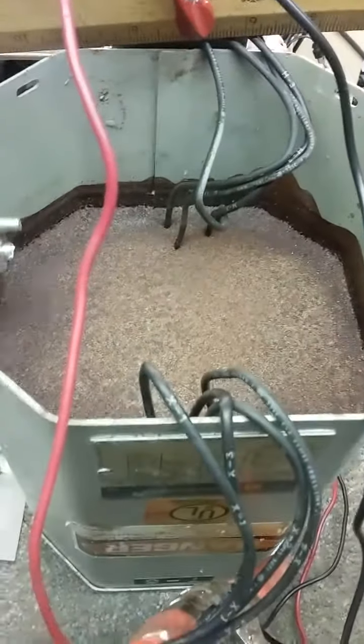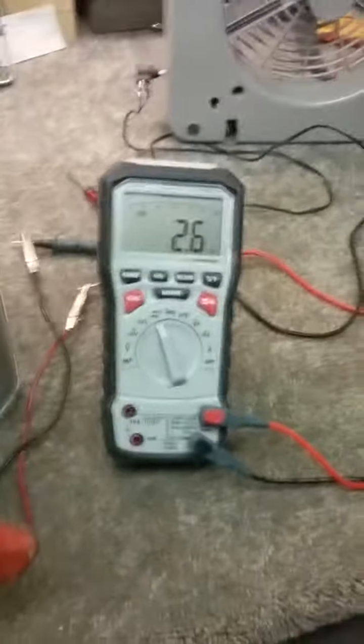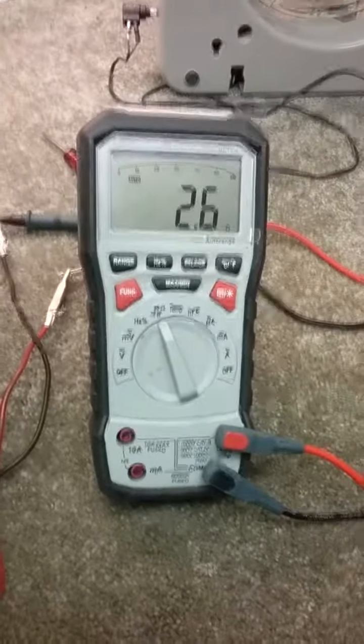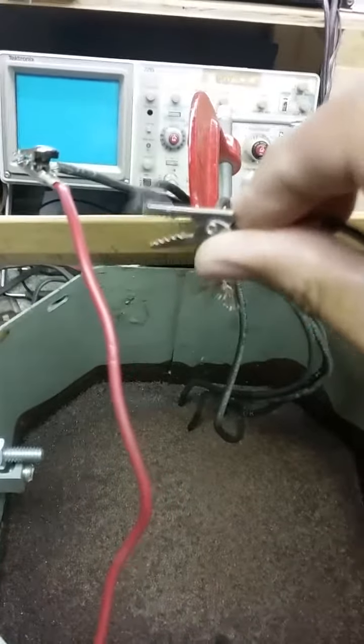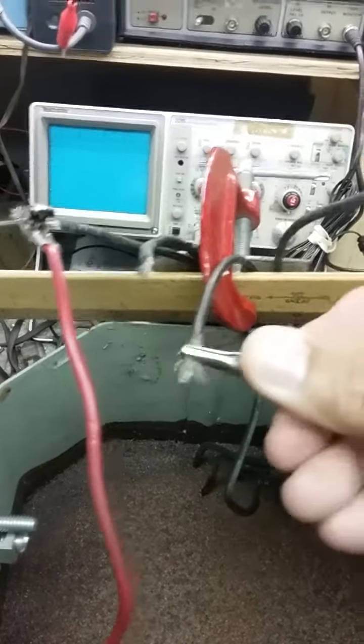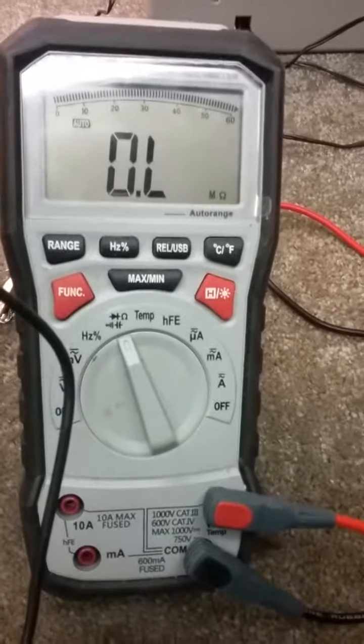This is a sand and resin dry cell, or dry transformer is what they call it. It is a single phase, so I can throw in single phase mains AC in here and play around with it to check everything. But we're going to continue checking the resistance. Right now, coil 1 of the primary is showing 2.6 ohms. So the second test I want to do is see if coil 1 to coil 2 is shorted out. And the way I'm going to do that is by jumping from coil 1 to either one, it doesn't matter, of the leads on coil 2. If there's a short, I'll get a reading, but I have no reading, so there's no short. That's assuming coil 2 is not open, which we will check right now.